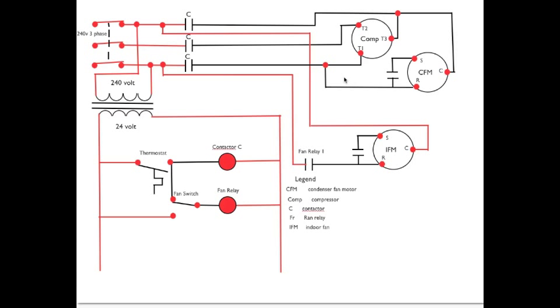The condenser fan motor, which has to be energized the same time as a compressor, is taken off of this set of contacts and that set of contacts, and it's single phase. Very commonly when you have a three phase unit, the only three phase part is the prime mover, which is a compressor.